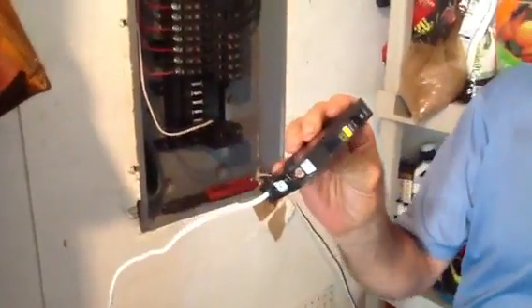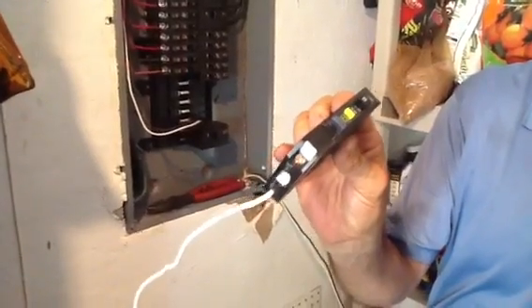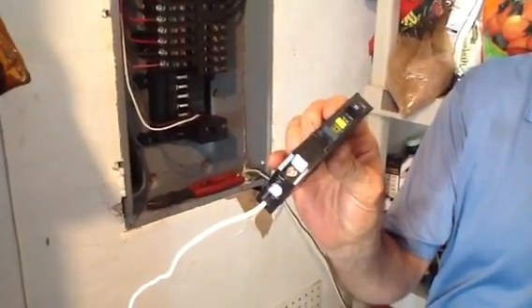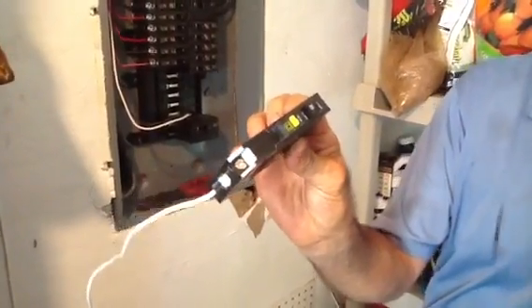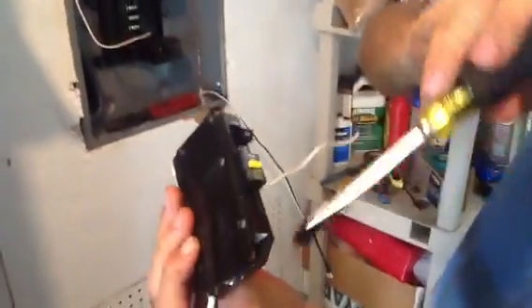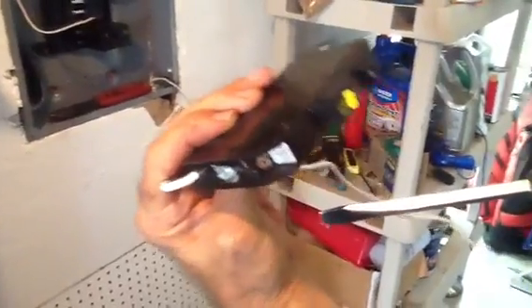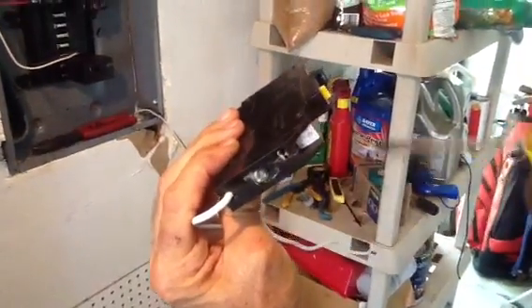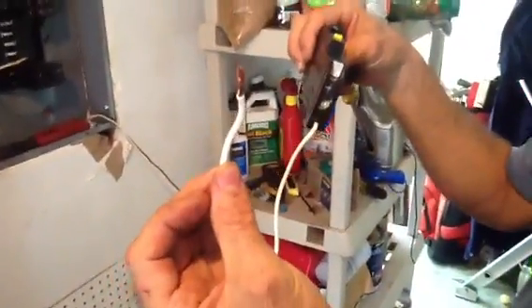What I want to talk to you about is how to install a Square D QO GFI breaker. This particular breaker is for the bathroom circuit. I want you to notice a couple of things here: you have a dark screw, you have a white screw, and then you have this pigtail that comes out of the end. This pigtail will go to the neutral bar of the electrical system.